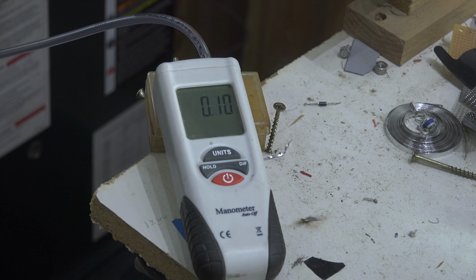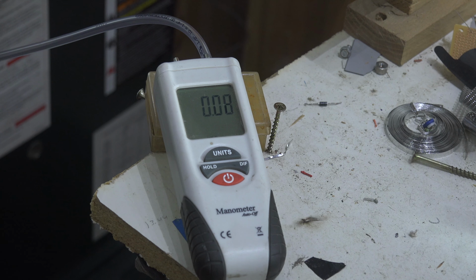If I had a high pressure drop in the supply, I'd be looking for some kind of blockages. But if I look overall at this whole system, the biggest problem in this system is the return is rather long and has a fair amount of resistance in it. The supply has virtually nothing. Okay, in the next video, I'm going to talk a little more about what other problems could come about with pressure in ductwork systems.